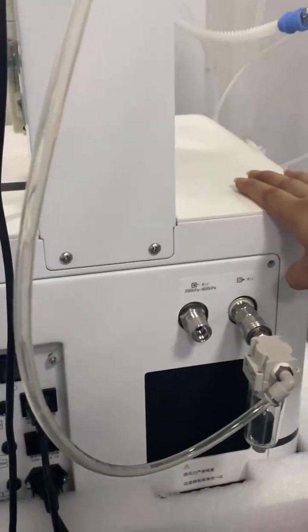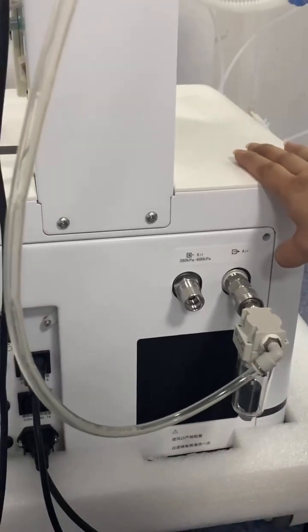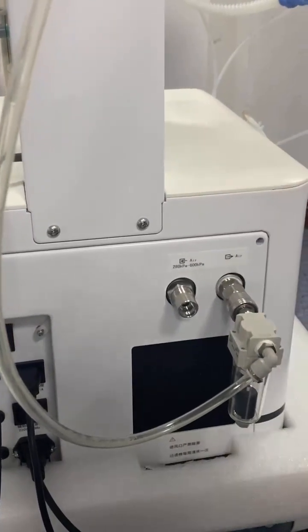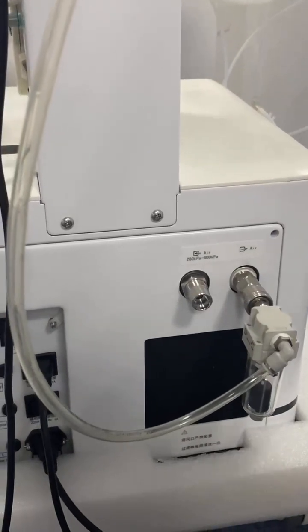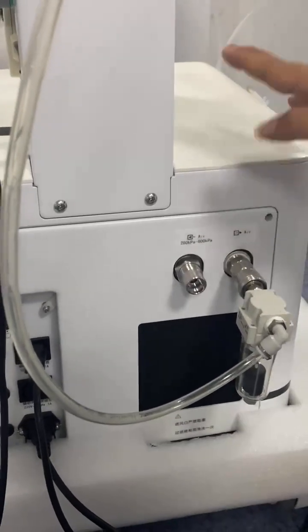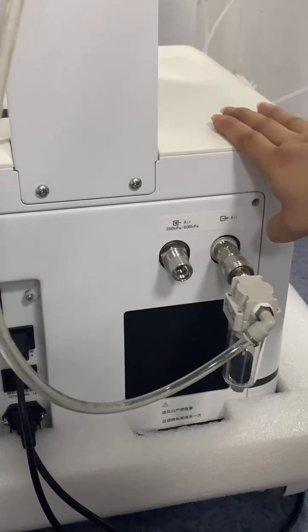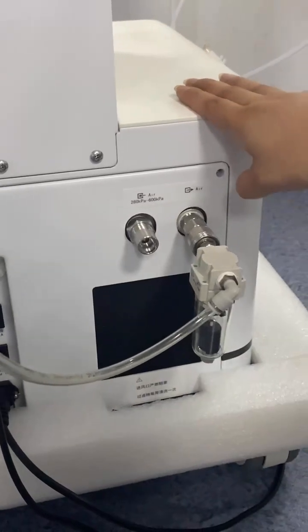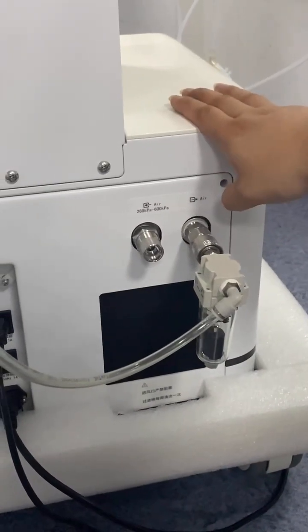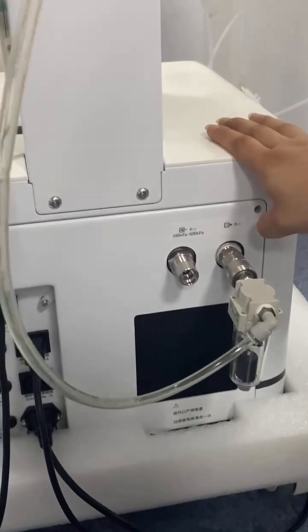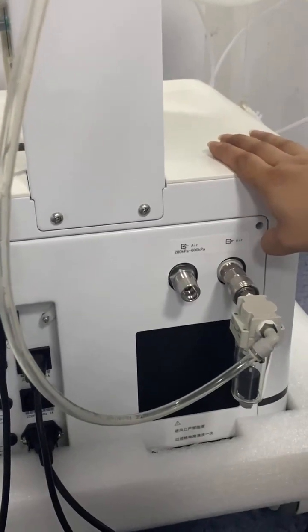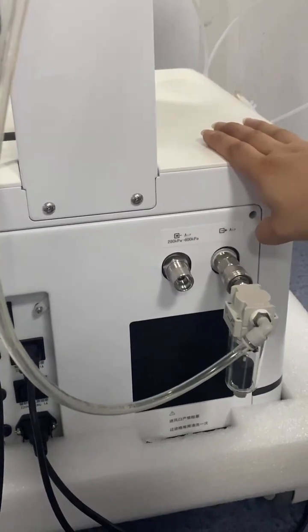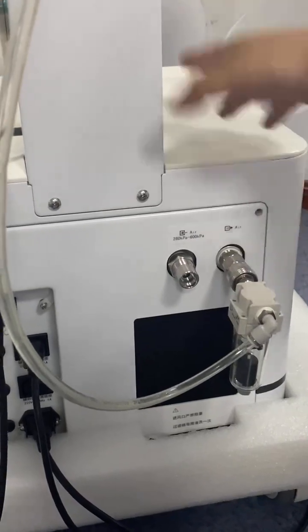Our air compressor will automatically test whether your central air has failed or not. If your central air supply is giving medical air, then our air compressor will stop. And if there is any failure from the other gas source, then our air compressor will automatically start and give the medical air. So it will ensure the patient always gets the gas inside and stays safe, with no danger.